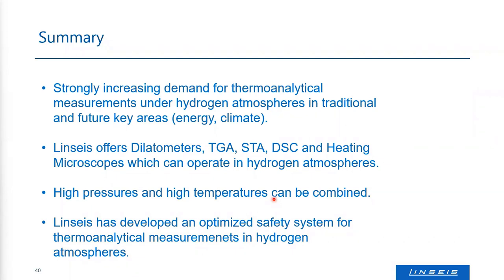Regarding safety for hydrogen measurements, we develop our own system. Nevertheless, it is highly recommended to discuss with us prior to hydrogen measurements what is necessary in your laboratory. You need to prepare your laboratory to make it safe — for example, implementing optical and acoustical warnings, our safety system, and possibly additional hydrogen sensors.